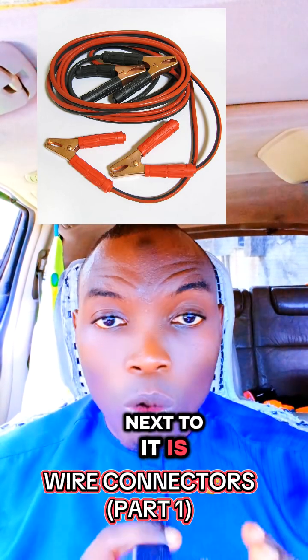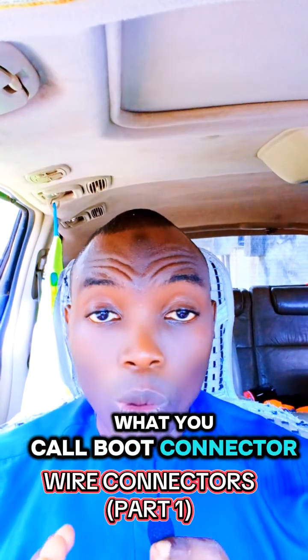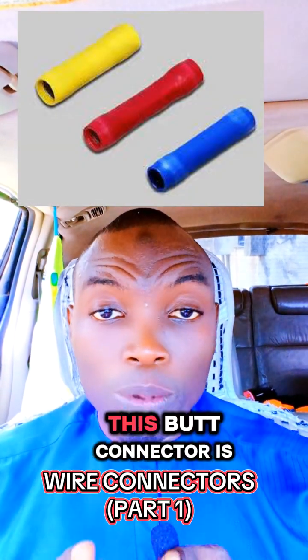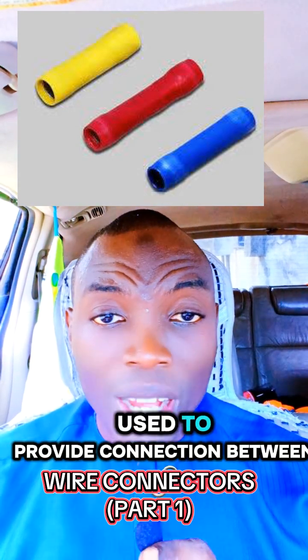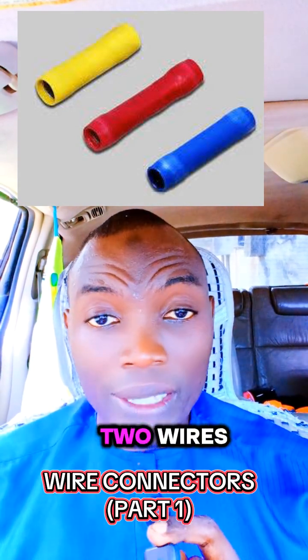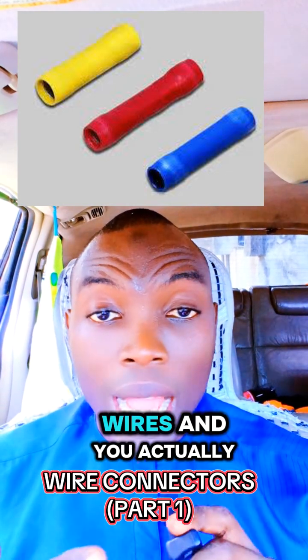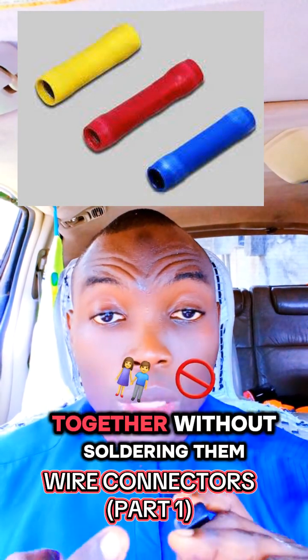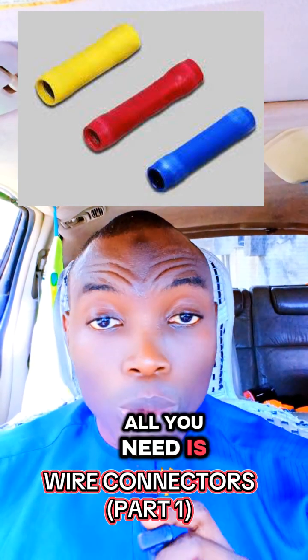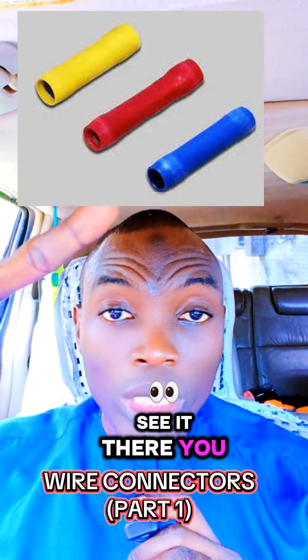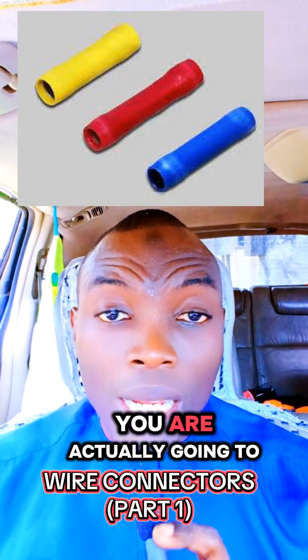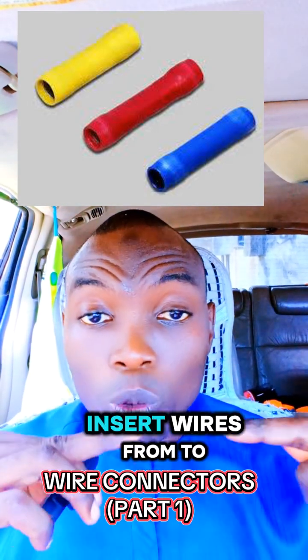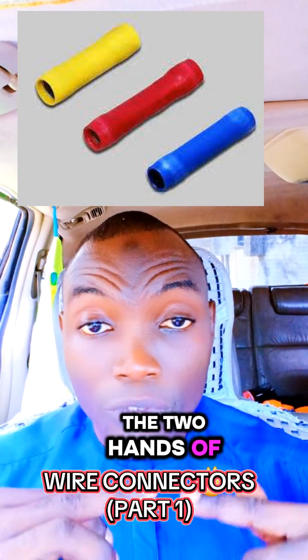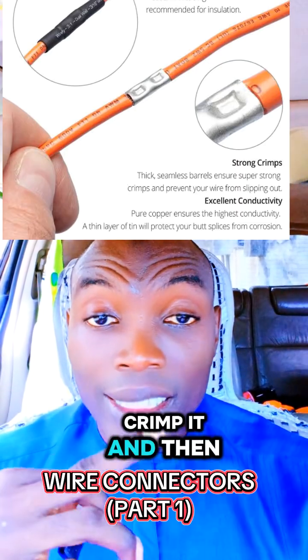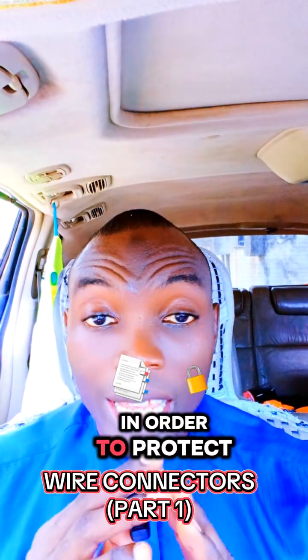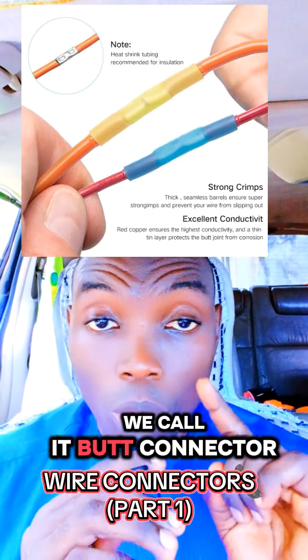Next to it is what we call the butt connector. This butt connector is used to provide connection between two wires. You have two straight wires and you want to join them together without soldering them. All you need is a butt connector. You can see it there. You are going to crimp it: you insert the wires from the two ends of the ferrule, crimp it, and then slide in the insulator in order to protect the joints. We call it a butt connector.